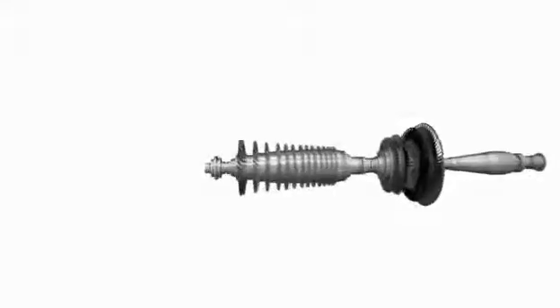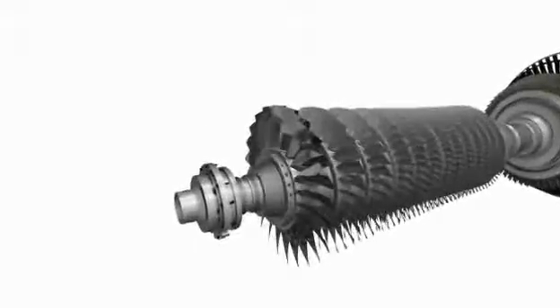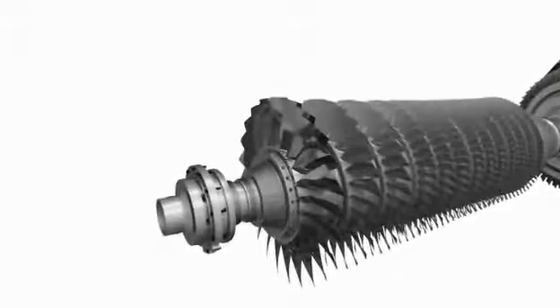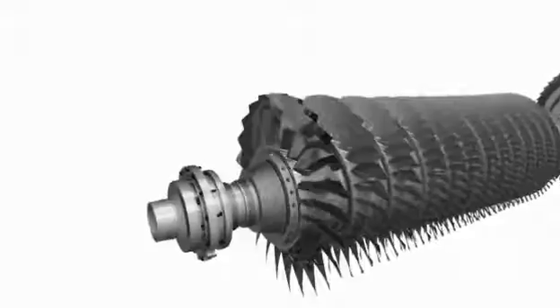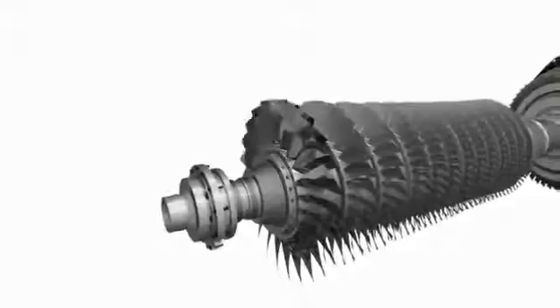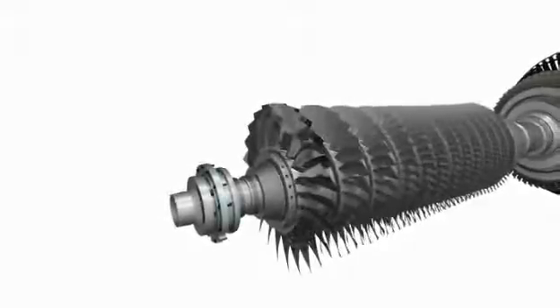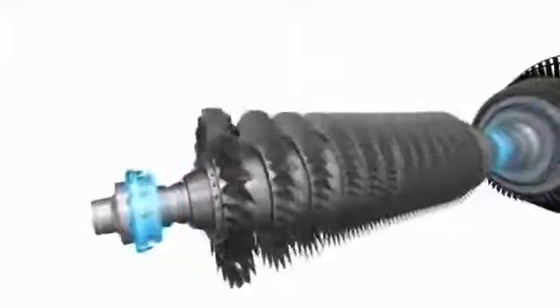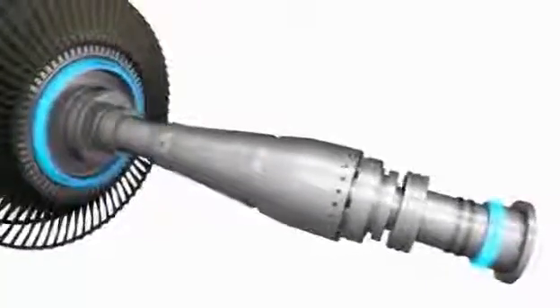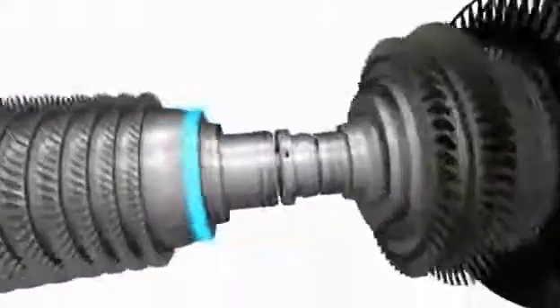The rotors incorporate the heritage of Siemens electron beam welding. The single rigid compressor rotor body ensures reliable, stable, and uniform run-up in hot or cold conditions. Axial blade attachment grooves allow blade replacement without rotor removal. The turbine discs are bolted to the compressor rotor and supported with mineral oil lubricated long-life tilting pad bearings. The balancing planes allow field balancing on-site without disassembly. Even in the early engineering phase, we can design in future maintainability and serviceability.